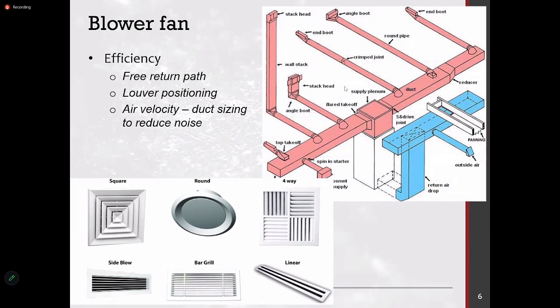Then air velocity and duct sizing, there is actually a complete design. Depending on your duct sizes, the air velocity will increase or decrease. So there are limitations. Generally, we have it in the range of 2 to 3 meters per second. If it is going to about 6 meters per second, you will hear a whistling noise. So that will also be a concern, and your flow rate will be the same, but if the air speeds are increasing, that could be a disturbance to whoever is inside.